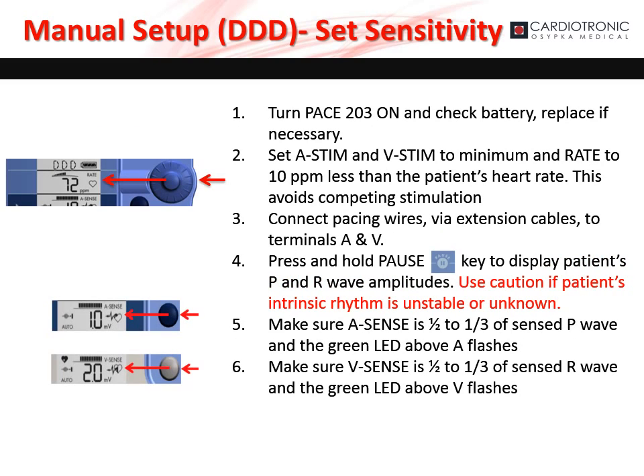To manually set up the PACE 203, first make sure that the device is on. Set A-STIM and V-STIM to the minimum value and set the rate to 10 beats per minute lower than the patient's heart rate to avoid competing stimulation. Connect the pacing wires via extension cables securely to the A and V terminals. Press and hold the pause button — the PACE 203 will display the patient's P and R wave amplitudes. Use caution if the patient's intrinsic rhythm is unstable or unknown. Make sure that A sense is one-half to one-third the P wave amplitude and the green LED above A is flashing. Next, make sure the V sense is one-half to one-third the R wave amplitude and the green LED above V is flashing.